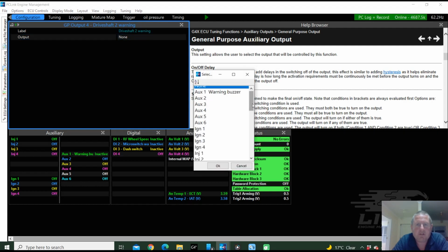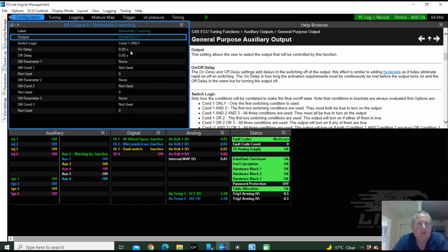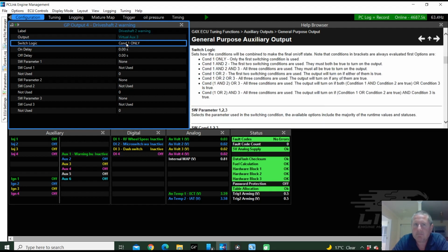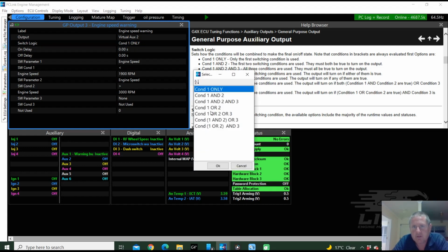We're going to have virtual auxiliary 3. Hey, did I set the other one up for an overspeed? Didn't check that, did I? I'll just use this little button here. Condition 1 only, so it's not going to give a warning for condition 2 because it's not set. So we're going to do condition 1 or 2.